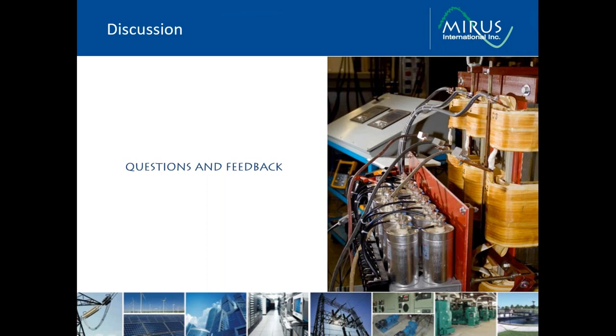And in our design, these are built on a common core. The three sets of reactors are built on a common core. The next question is about maintenance. What maintenance requirements are there for a wide spectrum harmonic filter, in our case a Lineator? So what we would recommend is that the filter be checked once a year, and the capacitance be checked at that time.